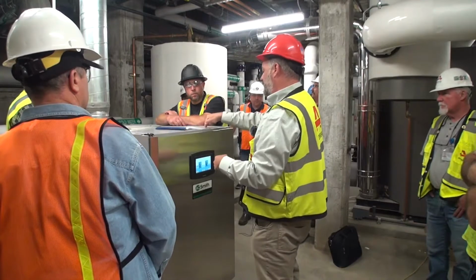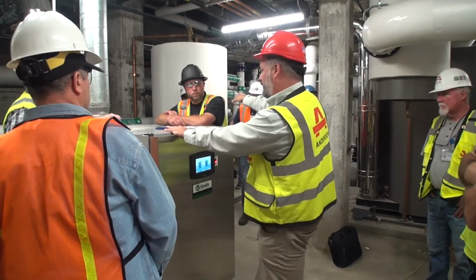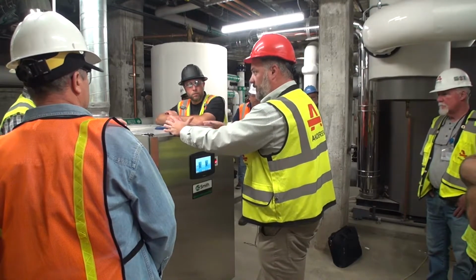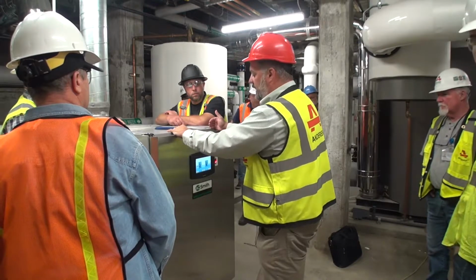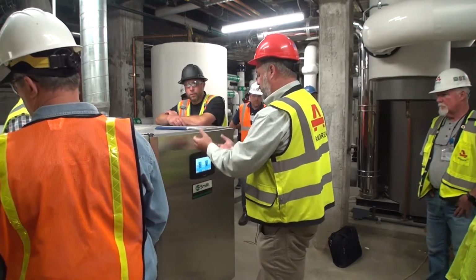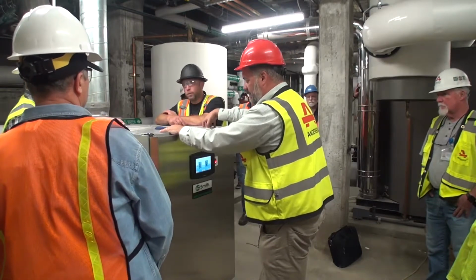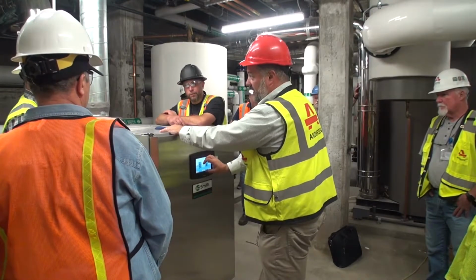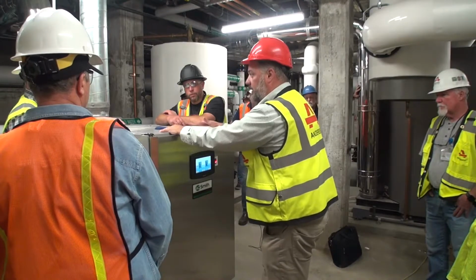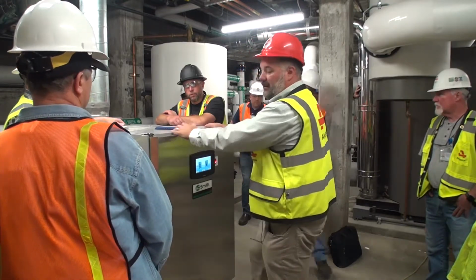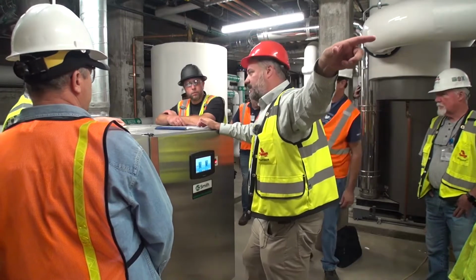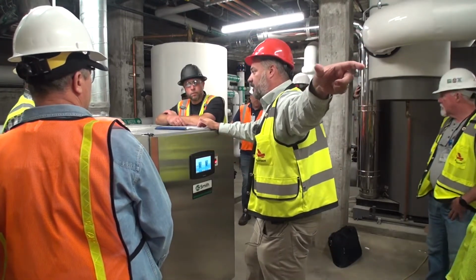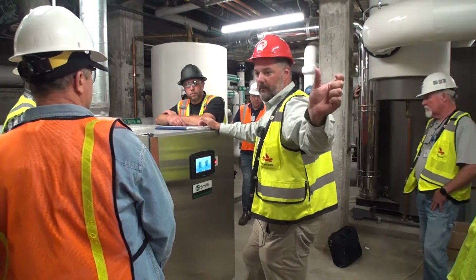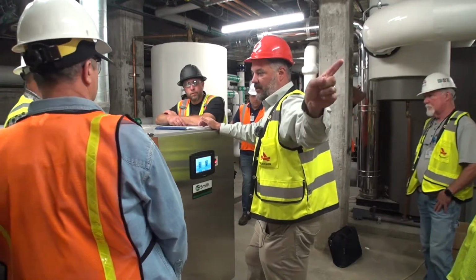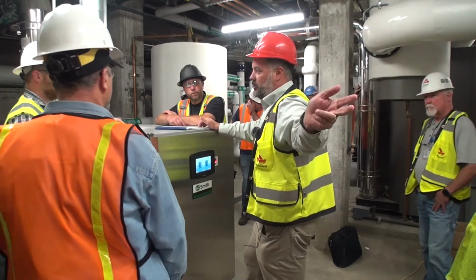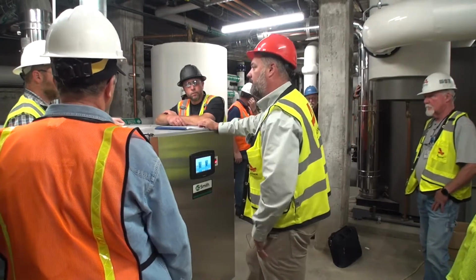If it was wired directly into here, that would be our enable disable to the boiler to turn on based on the temperature of the water coming through, and then it would go through its burner train 1, burner train 2. If there's an issue with it, then you're going to get an error code off of there saying, hey, I can't kick burner 1 on, and it'll showcase right away on here. We reroute over here, so that's now going to show when that burner is on or off on the controller. So you'll see a little power burner flame on there, and it'll have a number 1 for the number 1, number 2 for the number 2, and then both of them when they're both operating.